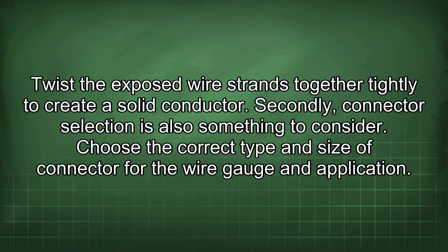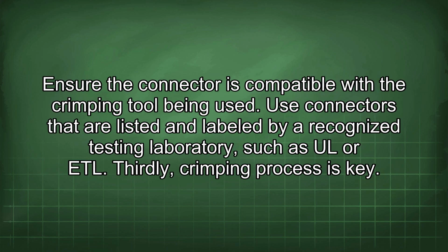Secondly, connector selection is also something to consider. Choose the correct type and size of connector for the wire gauge and application. Ensure the connector is compatible with the crimping tool being used. Use connectors that are listed and labeled by a recognized testing laboratory, such as UL or ETL.